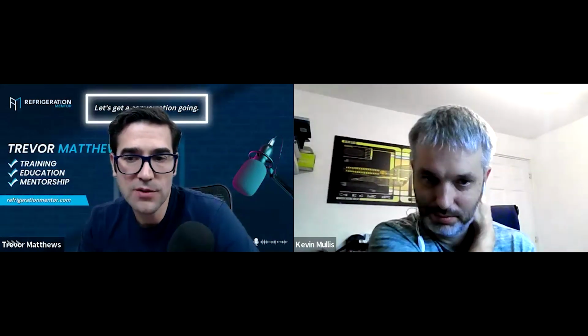And so the floating point, what Kevin was talking about: if you put that MOP close to the floating point, then all of a sudden the valve needs to open more, but it won't, because you hit your MOP. Because with floating suction, you want to increase the pressure of your suction as high as you can. The higher, the better, because as long as you maintain temperature, that's a huge energy gain.